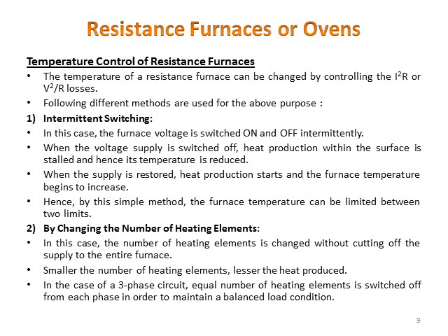In the case of three-phase circuit, an equal number of heating elements is switched off from each phase in order to maintain a balanced load condition. So in the case of three-phase supply, maintaining the balance of the load is important. So in order to maintain the balance of load, the resistance or elements per phase should be the same. So simultaneous switching of phase elements is required in the case of three-phase supply.